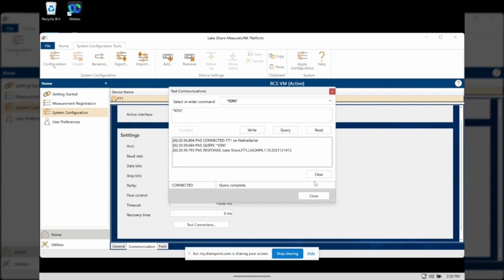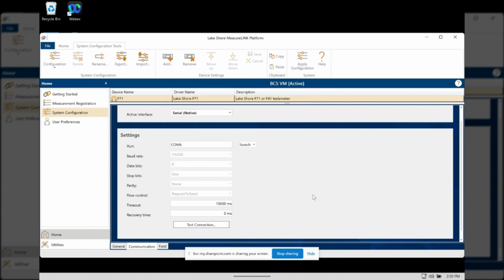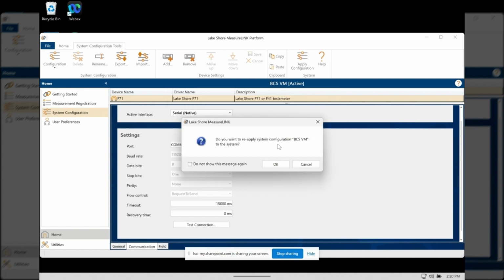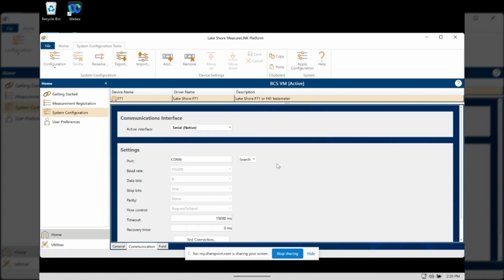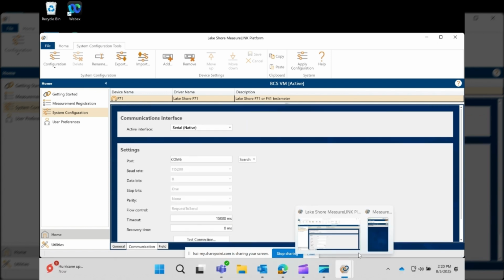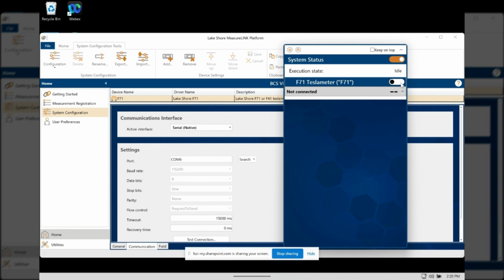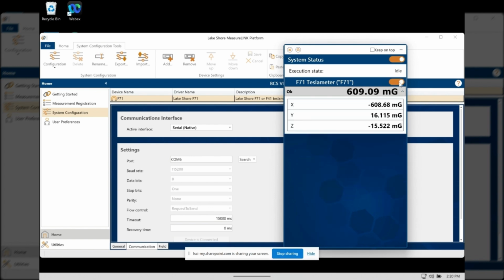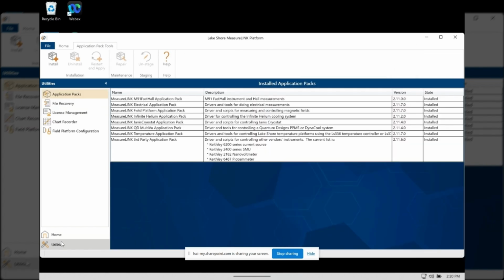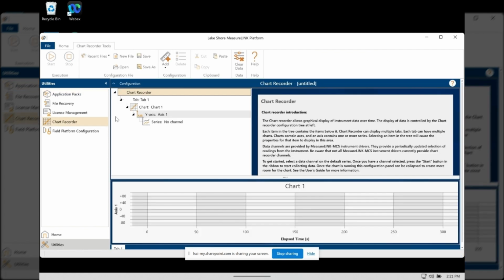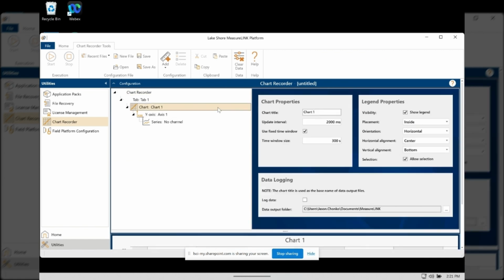So now that we have established communications with the instrument, we're going to apply that configuration, and then we are going to activate it by popping over to this execution window. Now we're going to read back directly. So we're live connected to the instrument, and we are reading directly from the instrument itself. So now we'll go to chart recorder, and this allows us to plot the magnetic field strength, or whatever parameters we're measuring, with respect to time in a sample configuration.